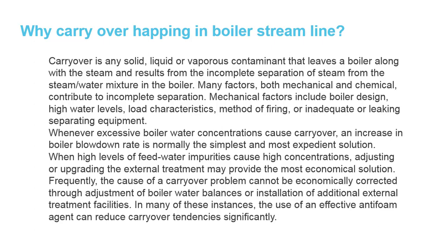Whenever excessive boiler water concentration causes the carryover, increasing the boiler blowdown rate is normally the simplest and most expedient solution. When a high level of feed water impurity causes the high concentration, adjusting or upgrading the external treatment may provide the most economical solution.